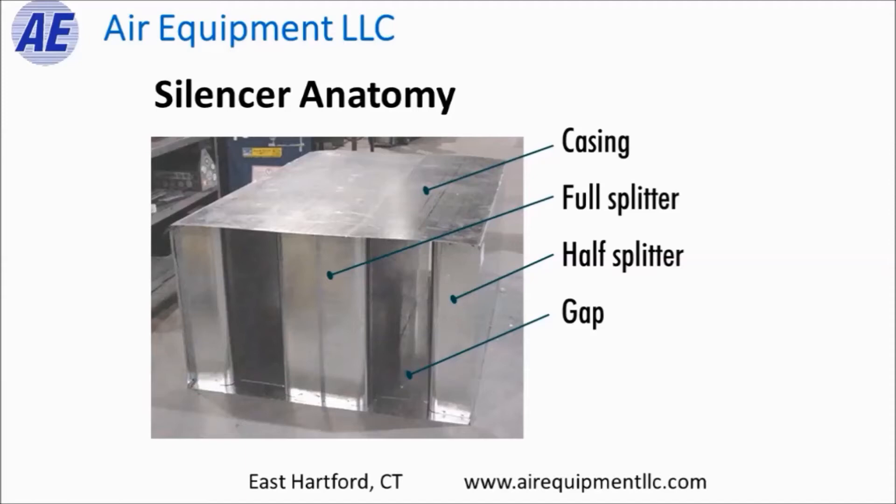As the air flows through the silencer, noise energy is captured in those modules — those splitters — and it gets trapped and dissipates among the fibers of the fiberglass. Essentially the noise is absorbed. So the noise level on the discharge side of the silencer is much quieter than what came in on the inlet side.